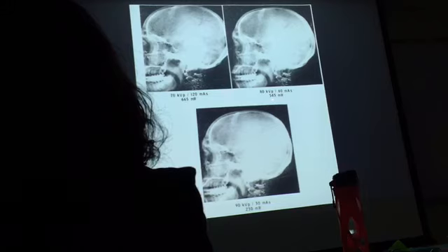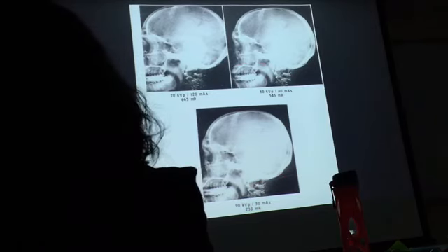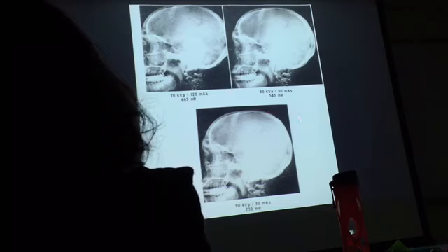120 milliroentgen less here. Now, if we go up here, 90 kVp, 30 mAs, so we cut the mAs in half again and increase kVp another 15%. Look, 230 milliroentgen less exposure. So less exposure in each one of them. The density has pretty much been maintained. However, the contrast has not been maintained.